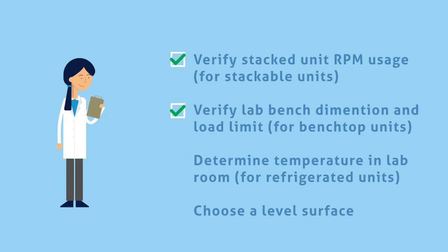And for a refrigerated unit, she must determine the temperature of her lab room, because if the space is too hot, it will cause compressor overload. Linda also acknowledges that for whatever unit she chooses, the lab surface designated to it must be completely level.